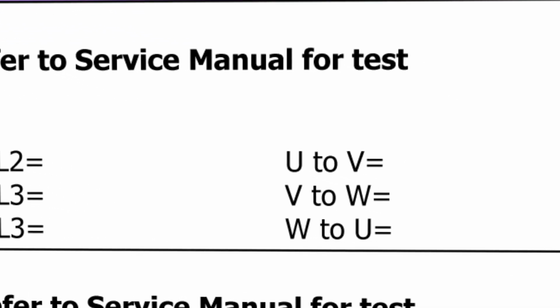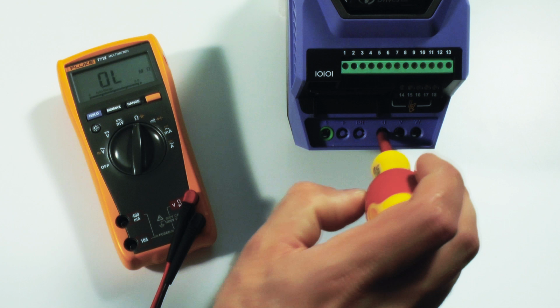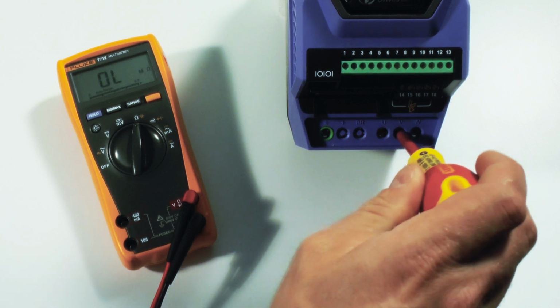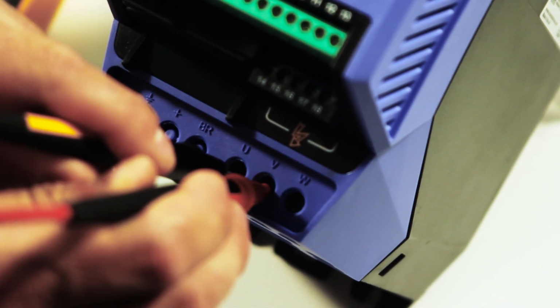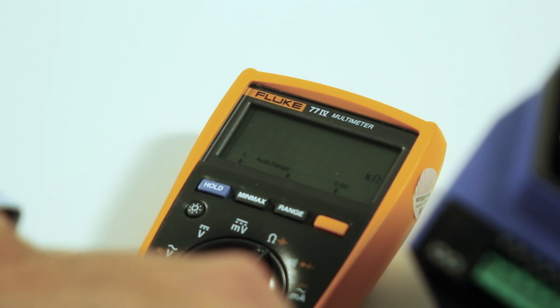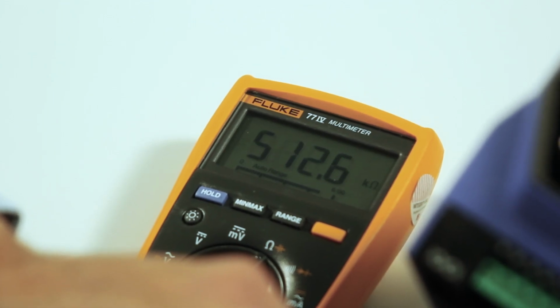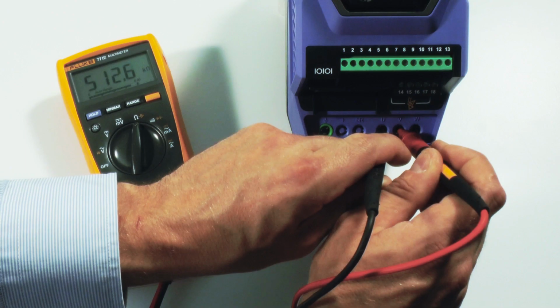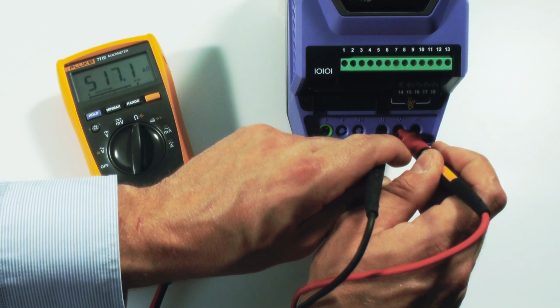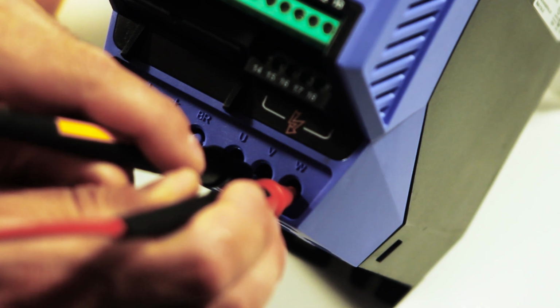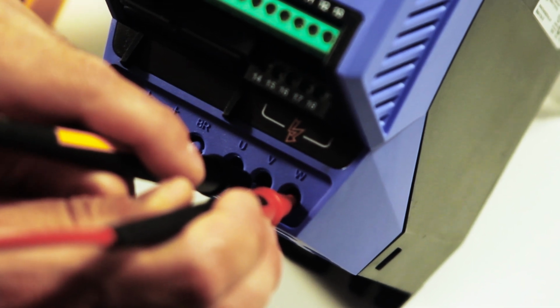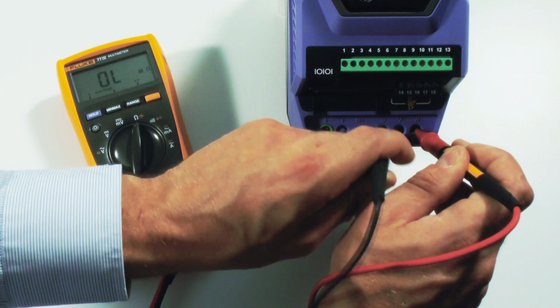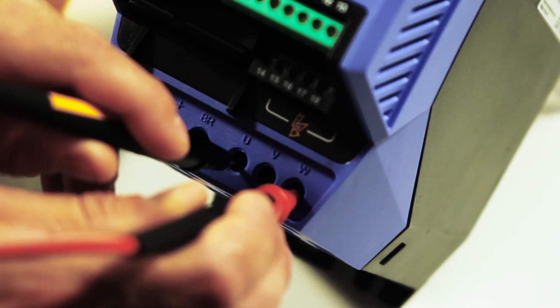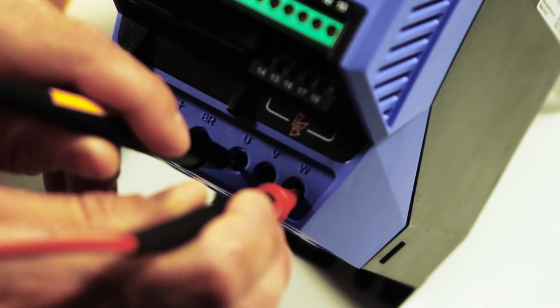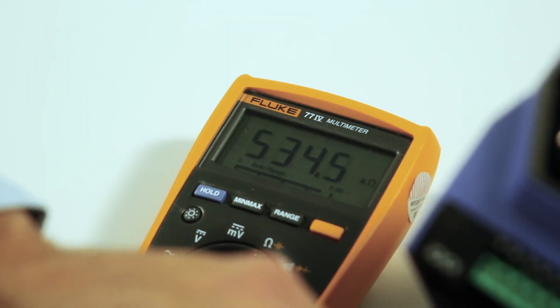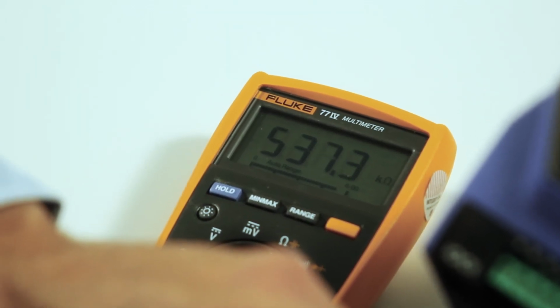Drive output check. Ensure the terminal blocks are screwed down using the terminal screwdriver. Place the black multimeter lead on U and the red lead on V phase. Please refer to the service manual for comparison readings. Repeat the process for the following test points. Place the black lead on V phase and the red lead on W phase. Then place the black lead on U phase and the red lead on W phase. Ensure measurements are balanced, or the same value, across each phase.